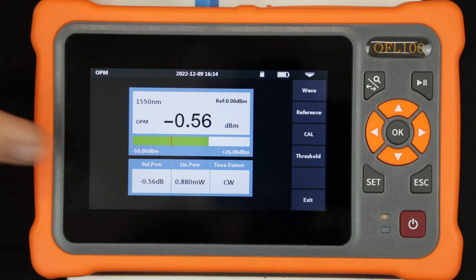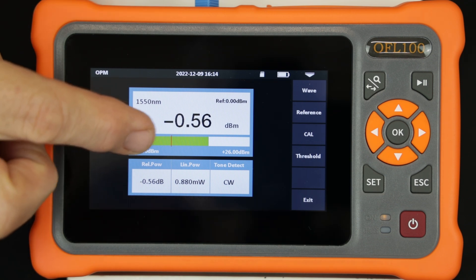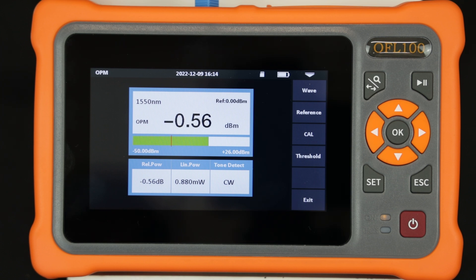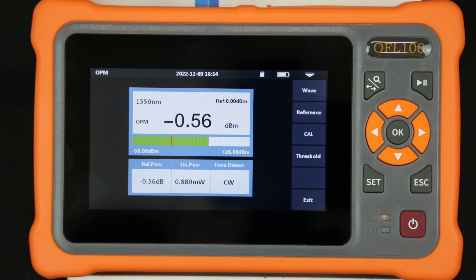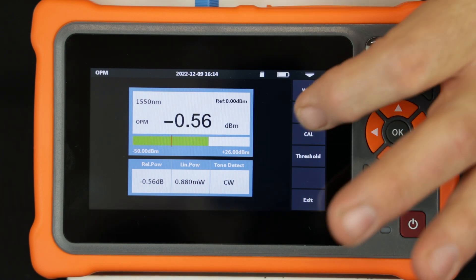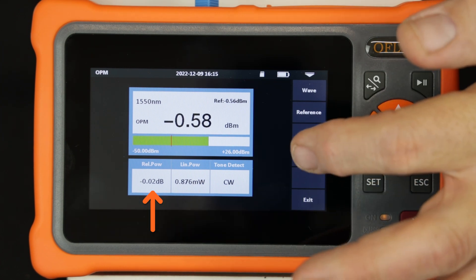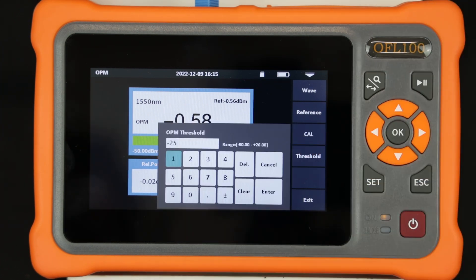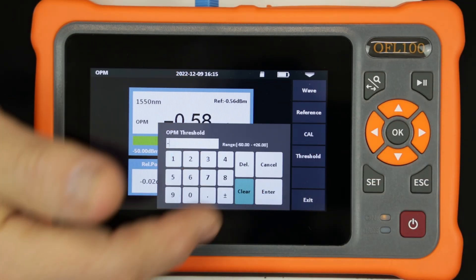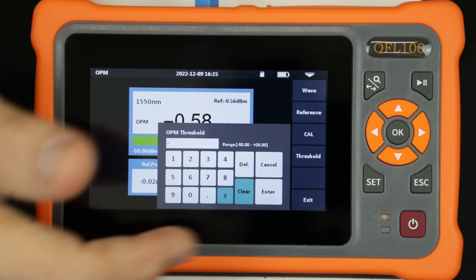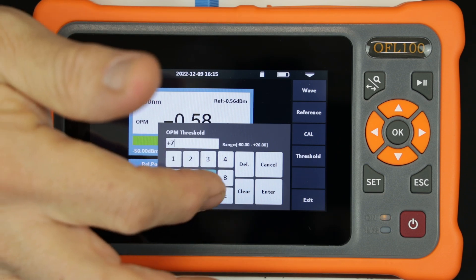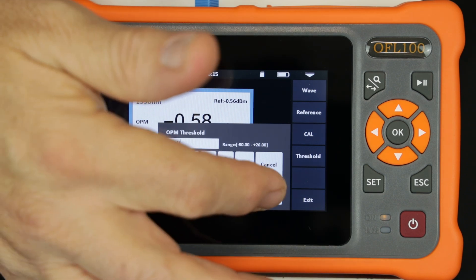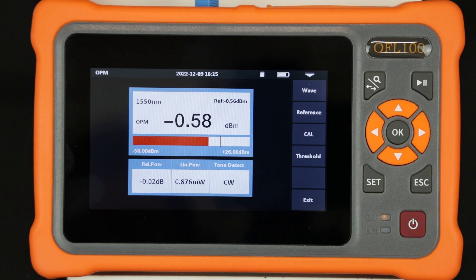The vertical line shows the threshold level. Optical power above this level will be shown with a green bar and power below the threshold is red. A 0 dB reference can be set for making relative insertion loss measurements. The measurement threshold can be set as desired. Here we set the threshold to plus 7 dBm and the bar graph is displayed red as the optical power is below the threshold. A threshold of minus 25 dBm is recommended.